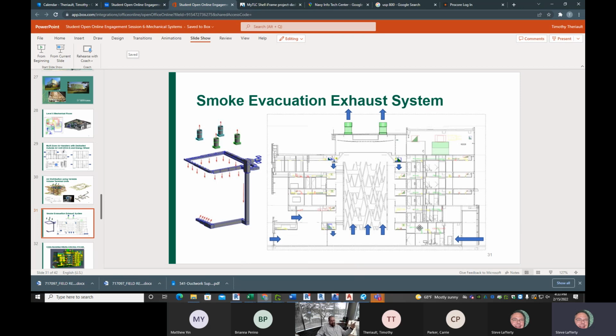So it's getting the other 90 to 190, whatever CFM from the outside coming straight in. And it's a temporary situation, so we're not conditioning any of this air. It just goes straight out. The point of it is to get all the smoke out of the system, get all the smoke out of the building so you can see, so you can escape if there's an event or an emergency or whatever you need to. That's what this system does with these 4 fans. And they're able to pull all of that volume of air just out of the atrium, get it out of your way so you can get out of the building.